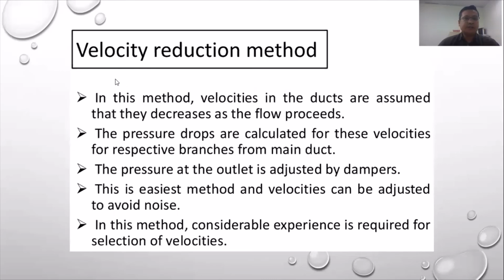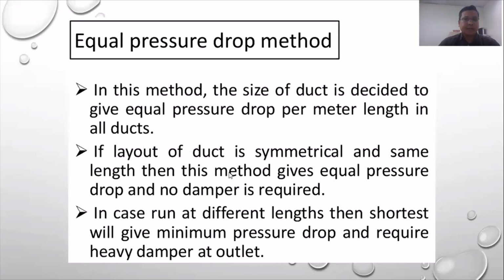So if we design by velocity reduction, the duct velocity is assumed to decrease as the flow proceeds. So we try to measure what the velocity is until the point area. And then by pressure also, we try to measure what the pressure should be supplied at the point.